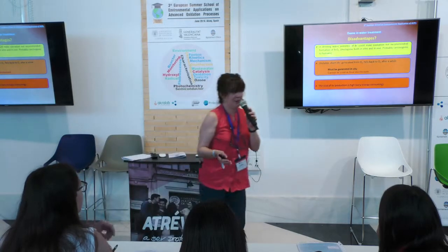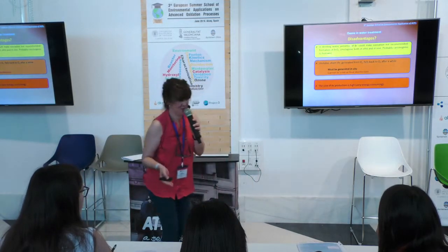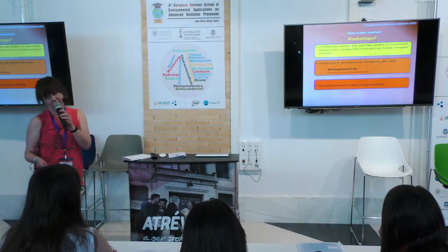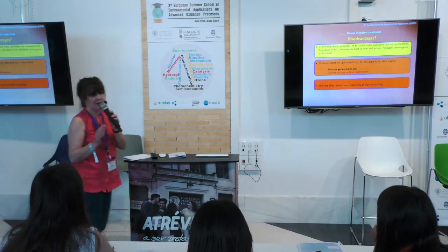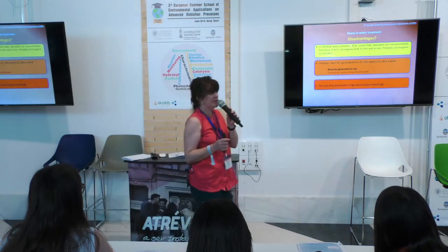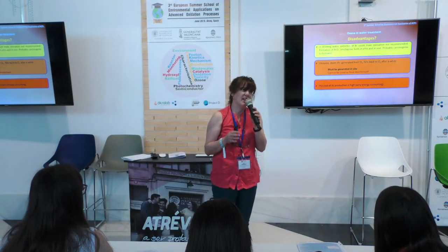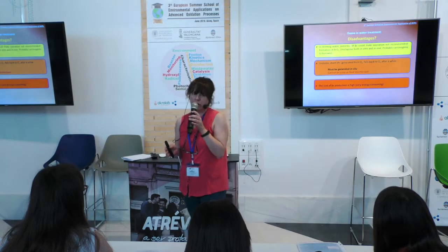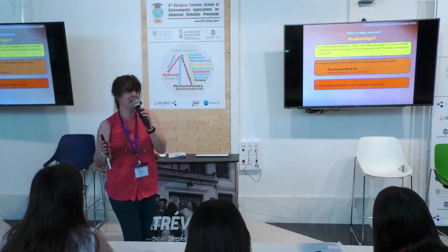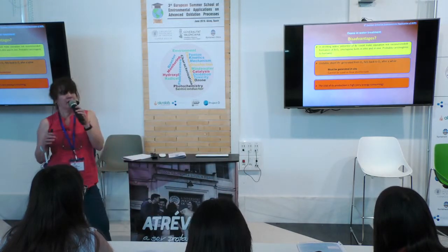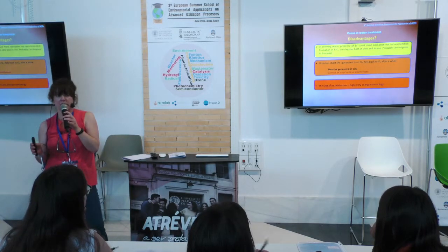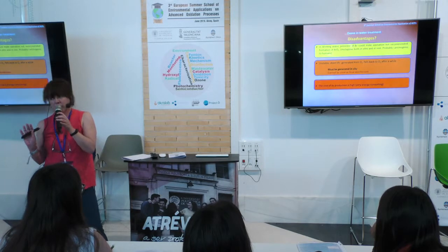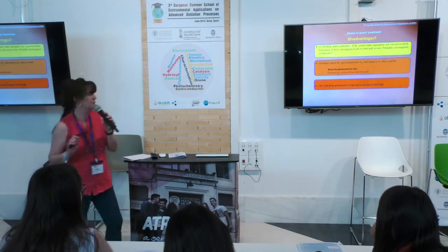Okay, but are there any disadvantages of the use of ozone? Of course there are. One of them, mainly related to drinking water, is if there is a high concentration of bromide in the raw water. During the ozonation, bromate is formed, and is probably carcinogenic to humans, so maybe ozone is not a feasible option.